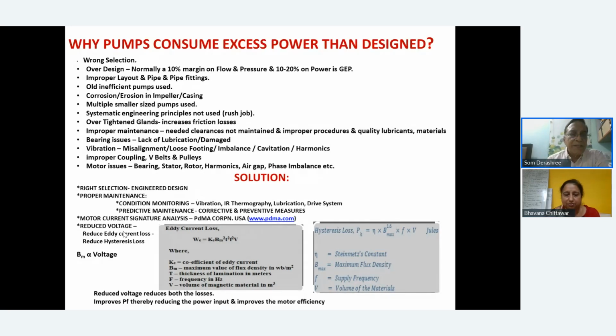Yeah. So now let's quickly, when you're talking about a pumping system, it consumes. So motor is one component, coupling is another component, and pump is the third component. So we have to really identify. In the pump, we have seen what kind of losses are happening. But in the motor, proper maintenance is required. You do condition monitoring, through vibration analysis, infrared thermography, lubrication analysis. You have a drive system, VFDs, etc. that are taken care of. Then in predictive maintenance, you have both corrective and preventive measures being taken care of.